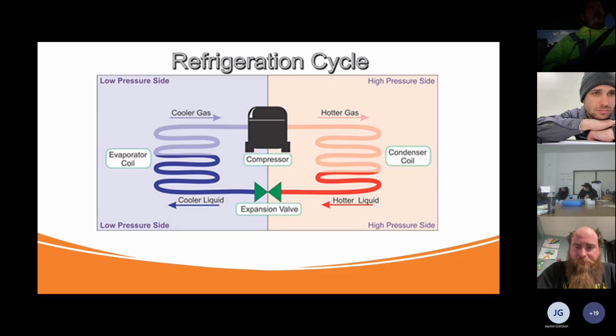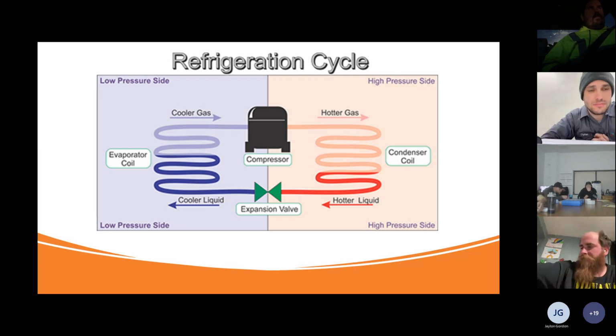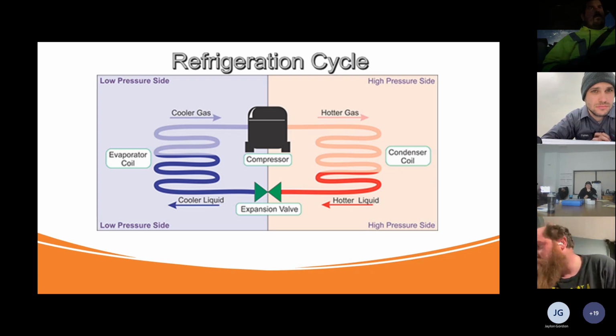And like Travis said, it really depends on what you're doing. If you're starting fresh with an empty system, you're obviously not going to put the full charge in via the suction. Dump it in the liquid. Once it's up and running, if you need to add additional gas, slowly meter it through the suction.